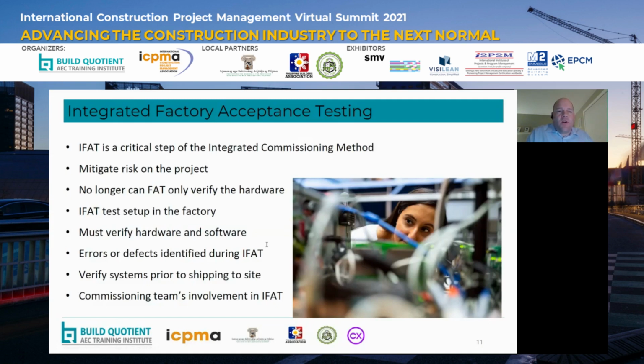So I've seen some pretty complex IFAT test setups in the factory. On the last project I worked with, there were 30 PLC cubicles at the southern end of the line and 30 PLC cubicles at the northern end of the line. But when these are being manufactured in the factory, all 60 cubicles are in one room, in a test setup. Everything's wired together, the HMI screens are all connected up, and essentially you have a very condensed version of what the installation will look like at site.